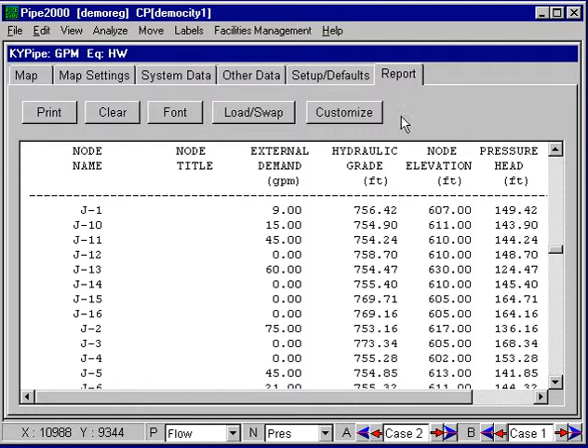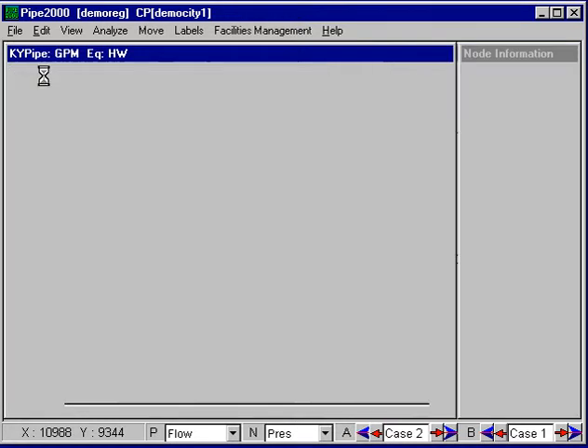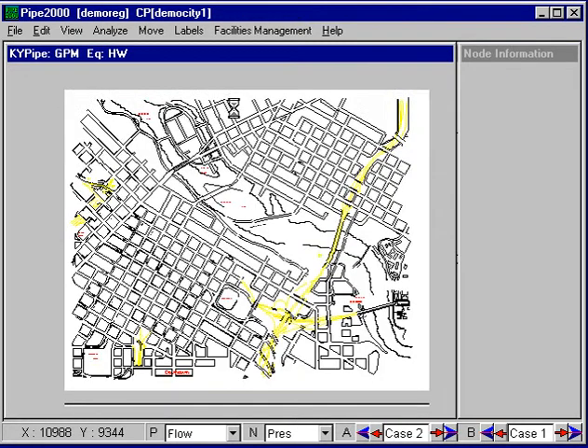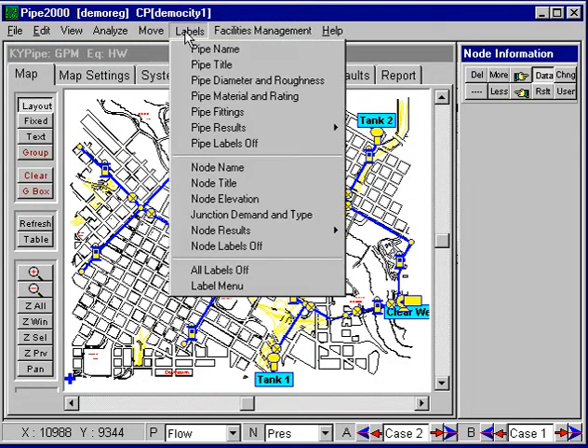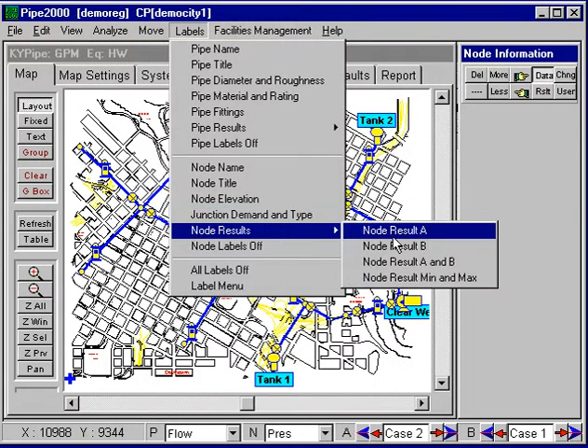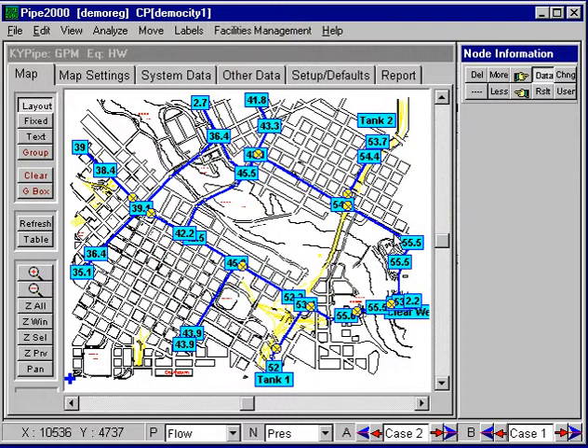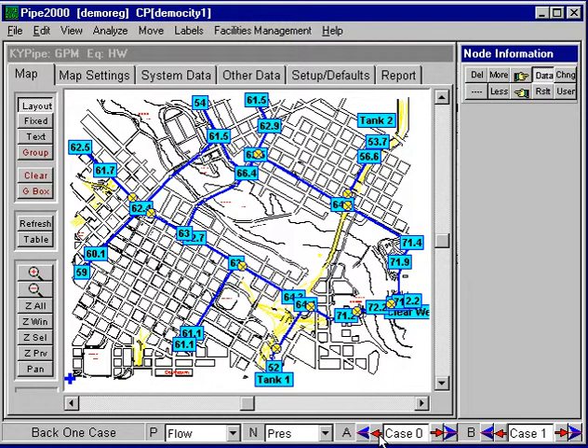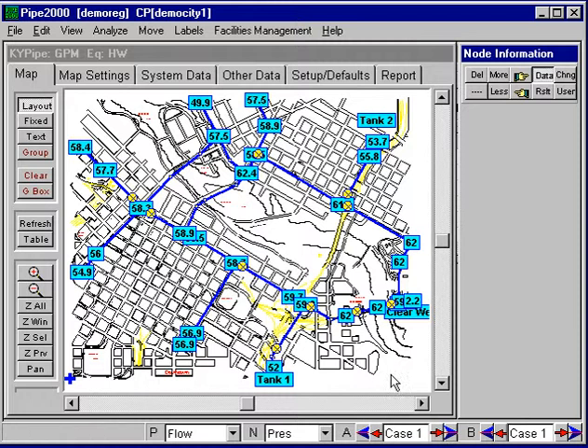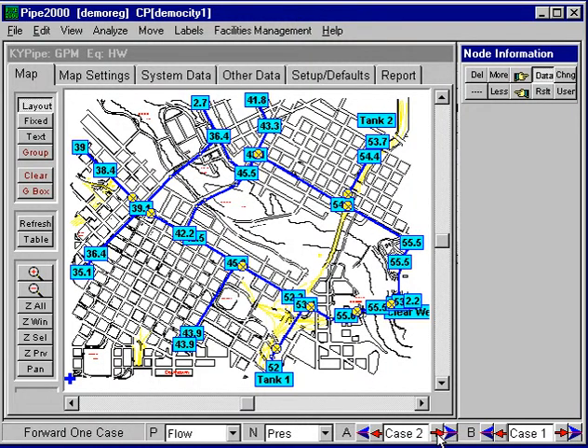Results for the nodes include pressures and pressure heads. Now we can also look at results graphically. We can turn on the labels and, for example, node results for pressures. Here are the pressures, and we can scroll through the cases. Here on case 2 we can go back — here's case 0 with the pump on, pressure here is 54. Case 1, pressure drops 4 or 5 psi because the pump is off. And for case 2, the pressure drops way down to almost 0 because of the fire demand.